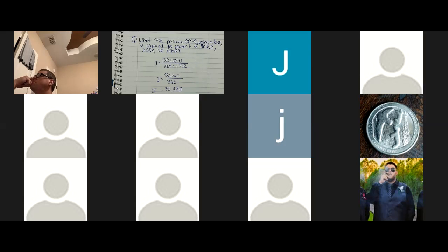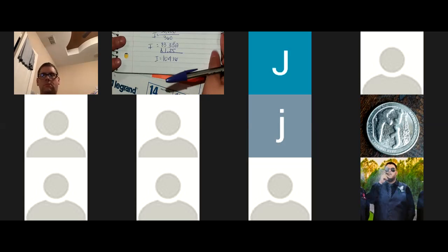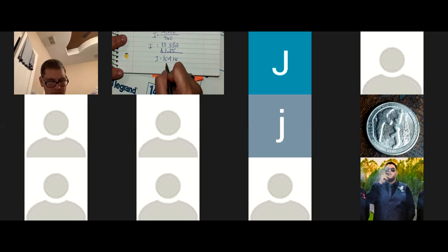I'm at 83 amps, so I'm gonna multiply that by 125%, times 1.25, I get 104.16. Right here, I can size up. So what am I looking at? Okay, yeah, you go. This is gonna equal a 110 amp fuse. And you got 4 of these questions.